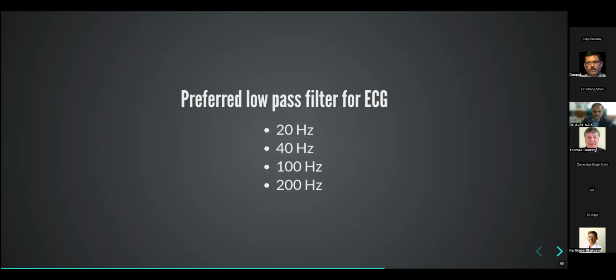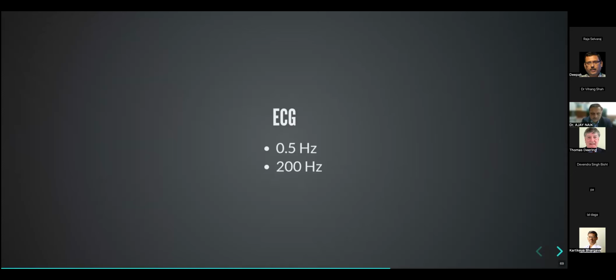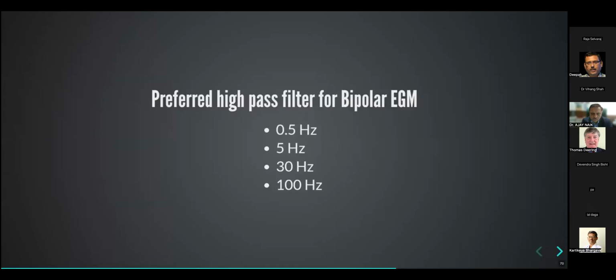But both are used. I would say it's preferable to try and use 100 or 200 hertz. But if you find it very noisy, even after you try other noise reduction and notch filters, then you can reduce it to 40 hertz, remembering that with that lower low pass filter, your ECG morphology is not going to be very good. So generally preferred is about 0.5 to 200 hertz. 0.5, or 0.67 of course, is the ACC recommended high pass filter setting.